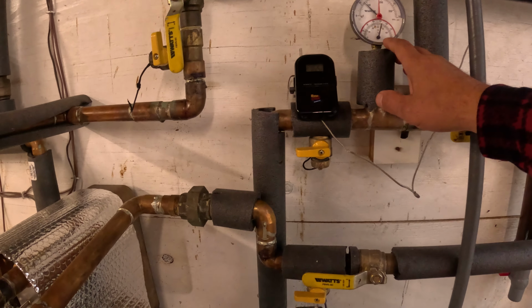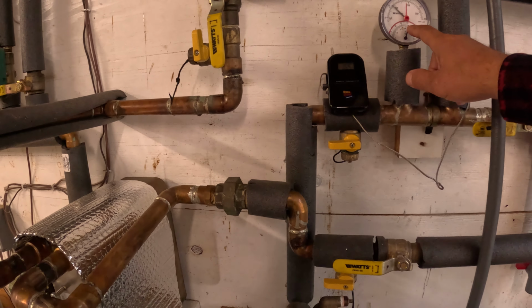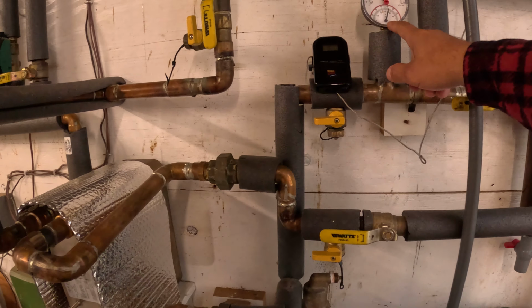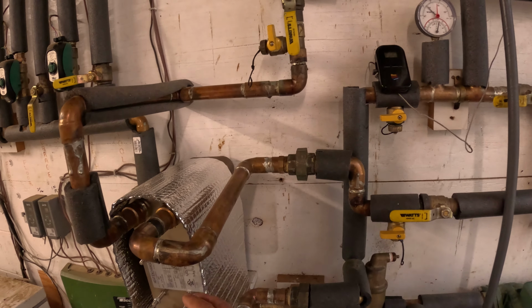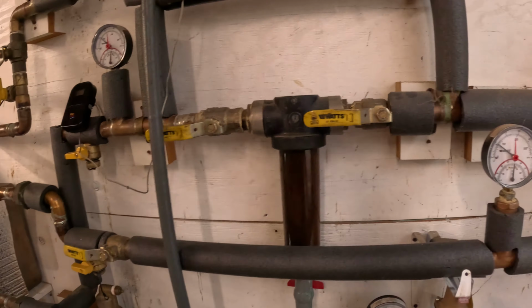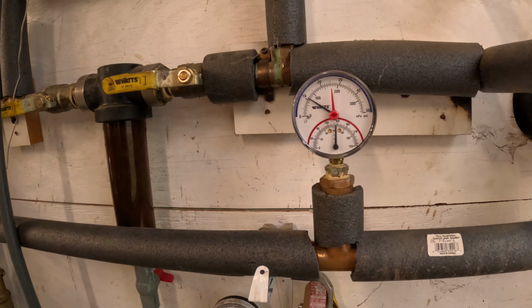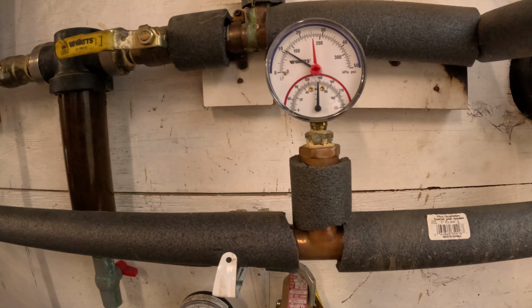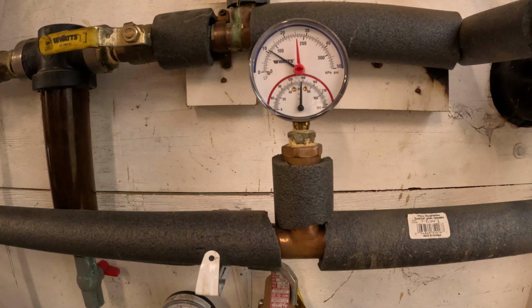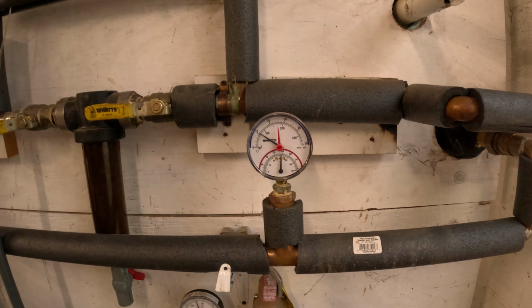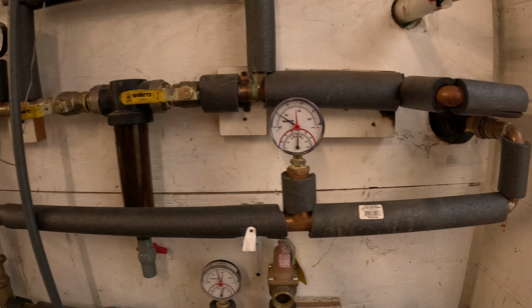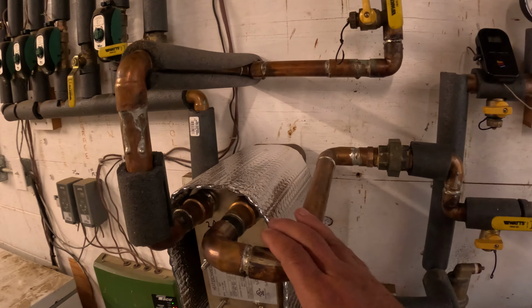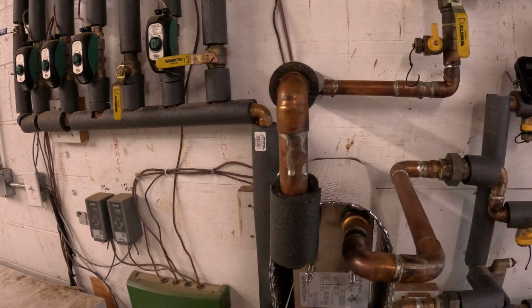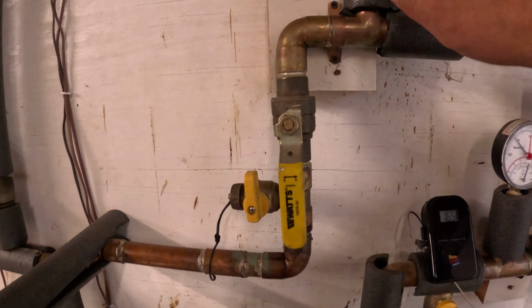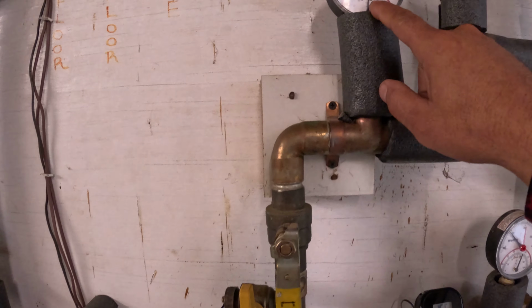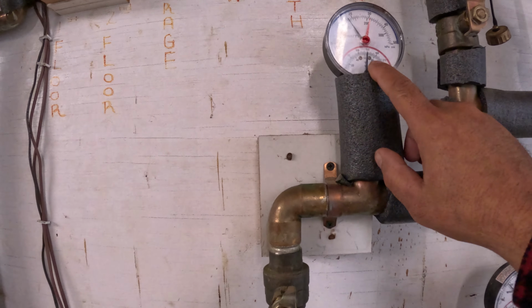So we basically come in, this looks to be about 160 degree water temperature or so coming in. It goes through the heat exchanger, and then it's coming back out at, according to that, somewhere around maybe 145. So we're pulling about 15 degrees out of the water with this heat exchanger for what is calling for heat, etc. And you can see on the return loop here we've got roughly 150 degree water temperature.